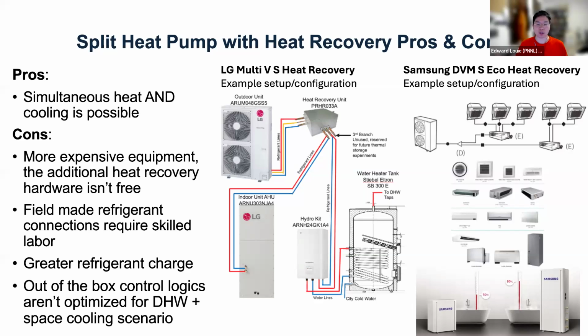Unfortunately, these systems are configured for heat recovery in a situation where, for example, your basement is quite chilly because it's below grade, and so you may want that basement air handler to be in heat mode while your upstairs is hot, and so you want that one in cooling, and so the temperature difference between your cooling side and your heating side isn't that significant.